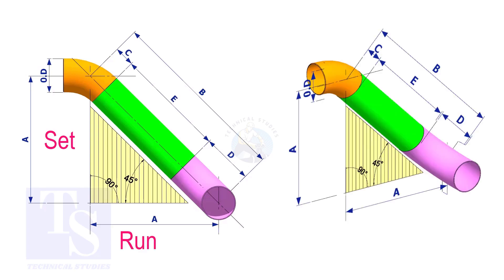In an offset, if the including angle is 45 degree, the set and the run shall be the same. If the value of the set and the run are equal, the value of the travel is set or the run, multiplied by 1.414.